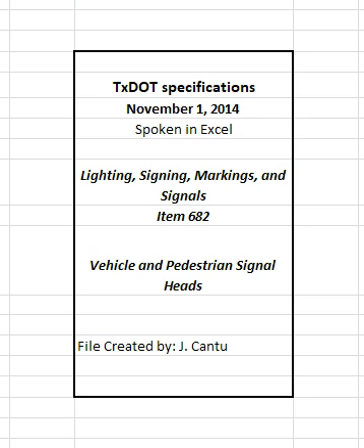3.2 Wiring. Wire each optical unit to the terminal block located in that signal section by means of solderless wire connectors or binding screws and spade lugs. Wire all sections of a multi-section signal face to the section terminal blocks in which the traffic signal cable is terminated. Maintain the color coding on leads from the individual optical units throughout the signal head, except for the traffic signal cable. Use solderless wire connectors or binding screws and spade lugs for connections to terminal blocks. Use binding screws and spade lugs for field wiring.